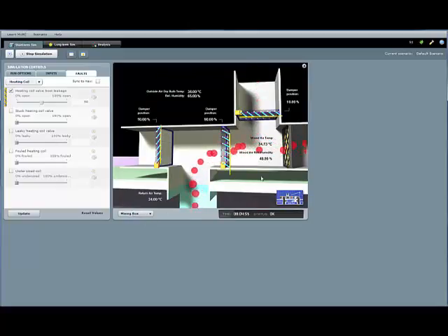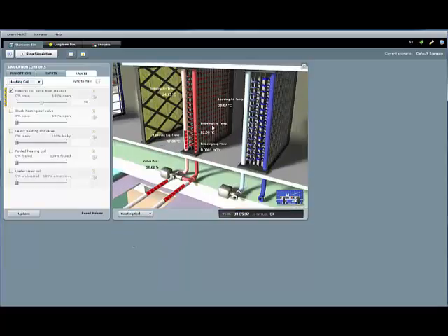The air is coming in at 24 degrees C. The heating coil is going to heat it up to about 29 degrees C, about 5 degrees C, and you can see there's modest flow coming through, going from 24 to 29.